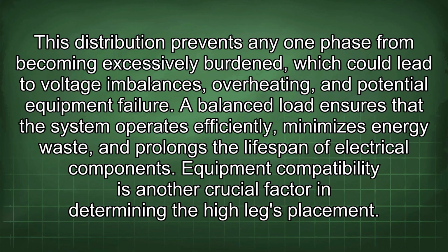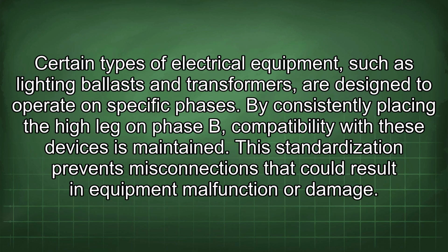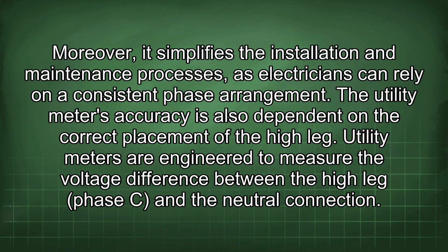Equipment compatibility is another crucial factor in determining the high leg's placement. Certain types of electrical equipment, such as lighting ballasts and transformers, are designed to operate on specific phases. By consistently placing the high leg on phase B, compatibility with these devices is maintained. This standardization prevents misconnections that could result in equipment malfunction or damage. Moreover, it simplifies the installation and maintenance processes, as electricians can rely on a consistent phase arrangement.